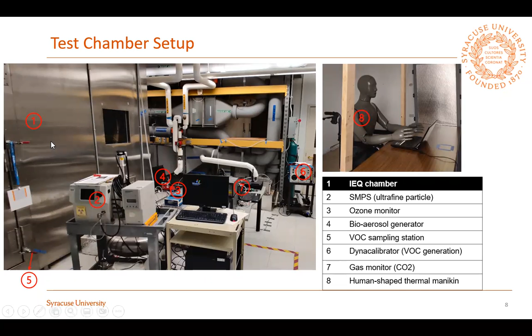We talked about how it is different, so we test under the steady state. We collected three samples, all under the steady state. The first is the background, with only the building materials and furniture in the room, which is our baseline. Later on, we start to inject the VOCs and the particles. The second presentation will give you some results on the virus with the particles, which we also inject. The second sample was collected at the steady state after the first injection to determine the challenge concentration right before we turn on the air cleaner. The third sample was collected after we turned on the air cleaner, when it reaches the second steady state. By comparing the two conditions, we can obtain the performance of the air cleaner, which is the reduction of the different pollutants.